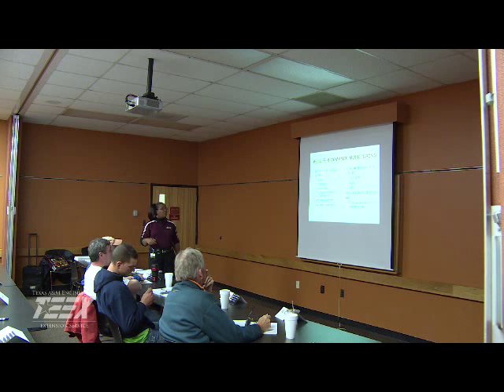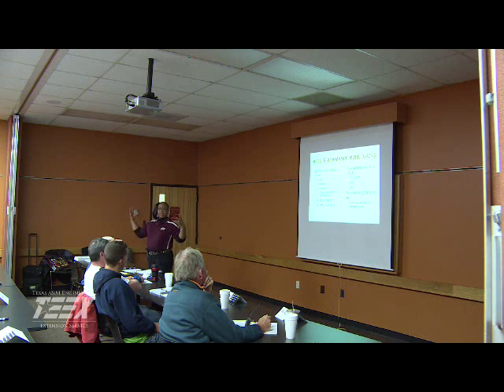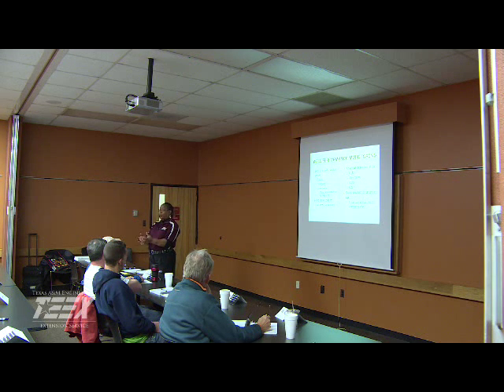Sand production at the start, again, this is something else that you can do as an operator as part of your process control. You can use an Imhoff cone. Are you all familiar with the Imhoff cones? Okay, it's a cone that's set up to show efficiency and how much sand. Usually it's an efficiency test that's done. And at the bottom it is graduated in milliliters per liter. And so what you do, well, mix sample, pour it in there and allow it to settle.